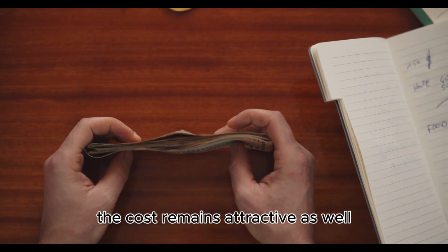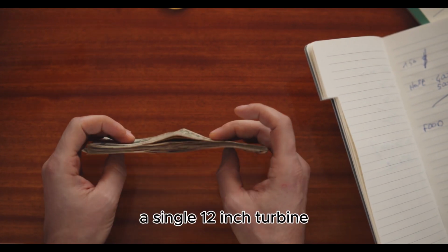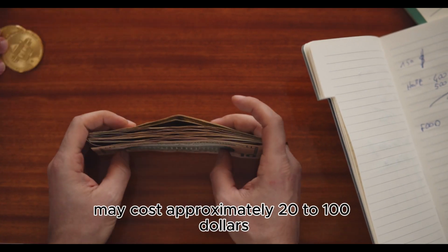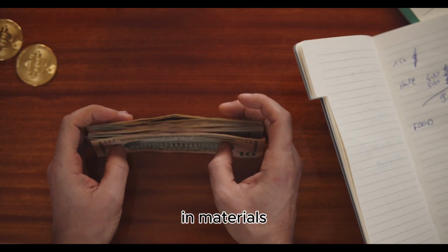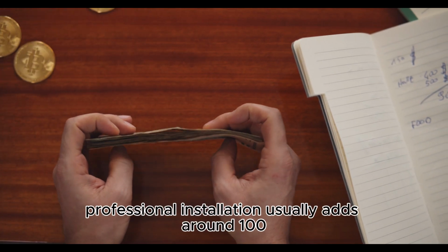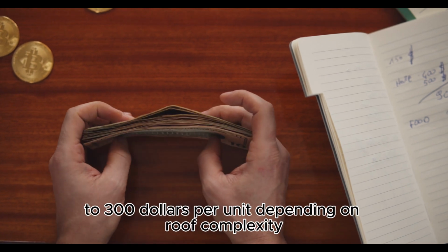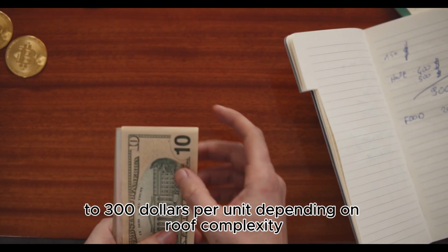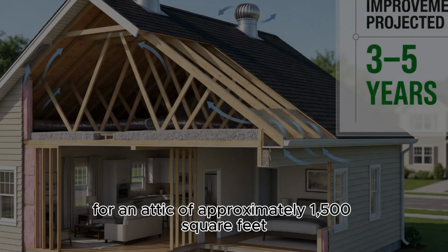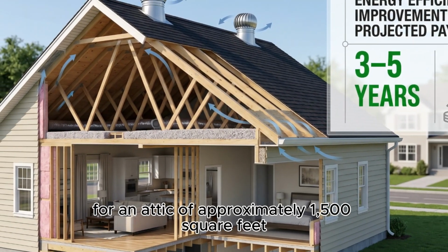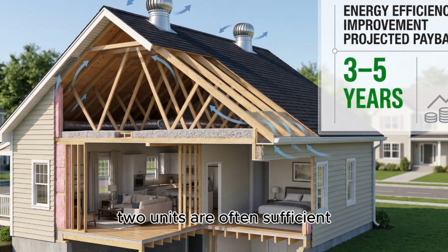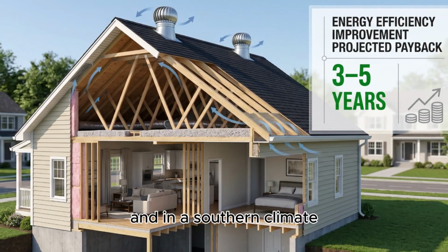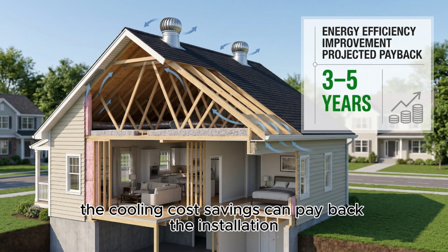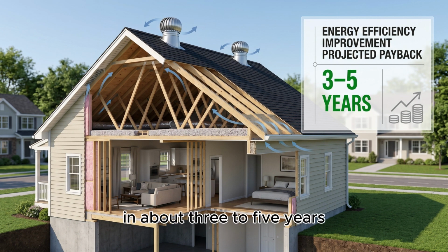The cost remains attractive as well. A single 12-inch turbine may cost approximately $20 to $100 in materials. Professional installation usually adds around $100 to $300 per unit, depending on roof complexity. For an attic of approximately 1,500 square feet, 2 units are often sufficient. And in a southern climate, the cooling cost savings can pay back the installation in about 3 to 5 years.